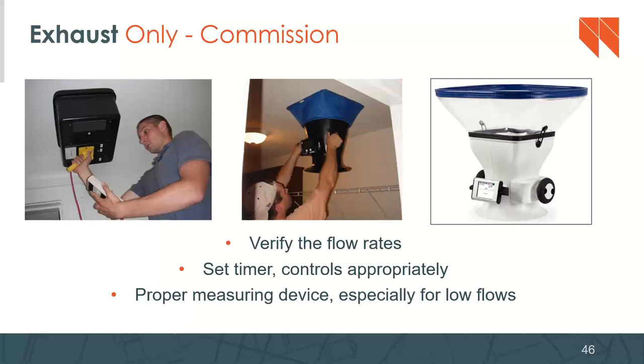I might have to take that back. Ventilation is quickly becoming the biggest issue that we see on a lot of our projects in terms of getting the flow rates right. Blower door testing and getting that infiltration down in passive house is difficult and tricky, and you've got to really be intentional about it. But on an Energy Star job, or even just a code level of air tightness, it's usually pretty achievable. But the flow rates for ventilation continue to be tricky. Every project, it seems like there is an issue. It's usually a fixable issue, but it's an issue that we find nonetheless.